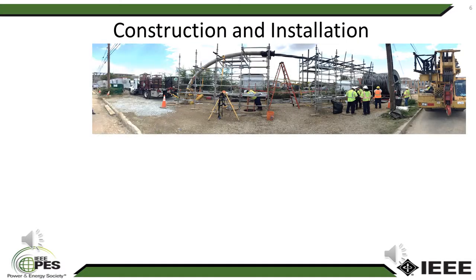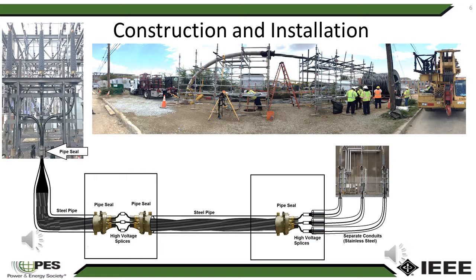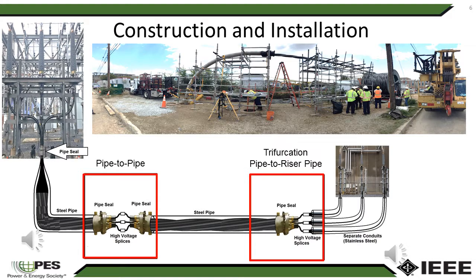During construction and installation, the triplex cables were installed from 1 cable reel between manholes and between one of the manholes and the substation. 2 different manhole configurations were utilized. The first involved triplex cable to triplex cable, as might be encountered during a conventional splice location and a regular pipe-type circuit. The other configuration involved a triplex cable to individual steel riser pipes to simulate a trifurcating manhole that might also be encountered in a retrofit project.